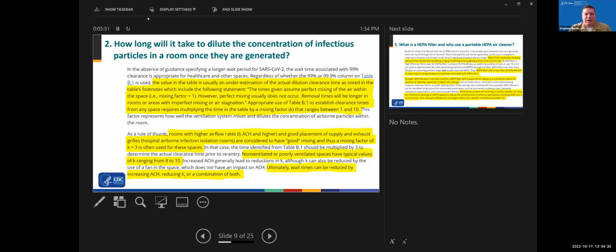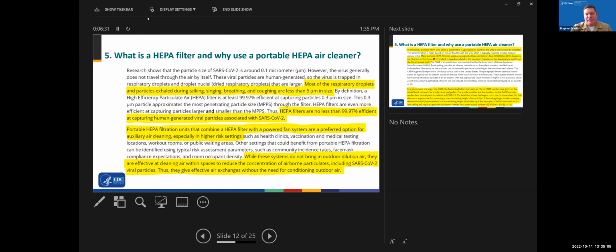In general, rooms with higher airflow rates, like 6 air changes per hour, with good placement of supply and exhaust grills, have good mixing, and we typically give them a mixing factor of 3. So we'd have to multiply the time in that table by 3. Unventilated or poorly ventilated spaces can have mixing factors up to 10. So when you apply your mixing factor, you get a very unwieldy time to clear particles. You can reduce those wait times by increasing the air changes per hour, reducing the mixing factor, or implementing better mixing in the space, or a combination of both. And that FAQ has example calculations and an example problem on how to do that.